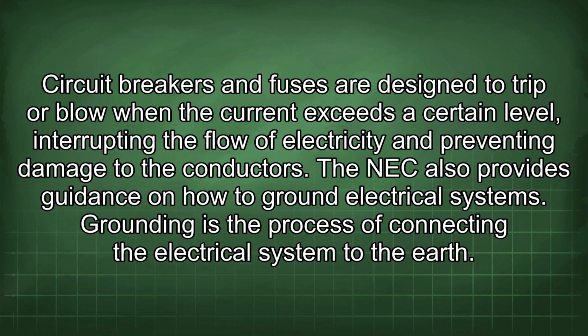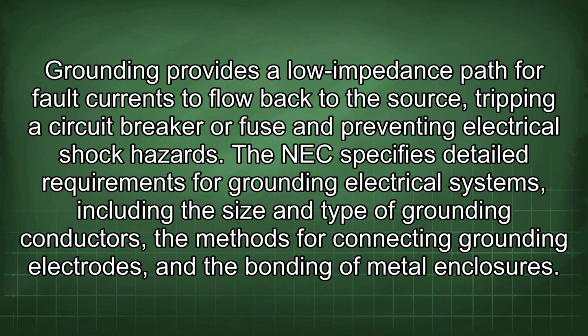The NEC also provides guidance on how to ground electrical systems. Grounding is the process of connecting the electrical system to the earth. Grounding provides a low impedance path for fault currents to flow back to the source, tripping a circuit breaker or fuse and preventing electrical shock hazards. The NEC specifies detailed requirements for grounding electrical systems, including the size and type of grounding conductors, the methods for connecting grounding electrodes, and the bonding of metal enclosures.